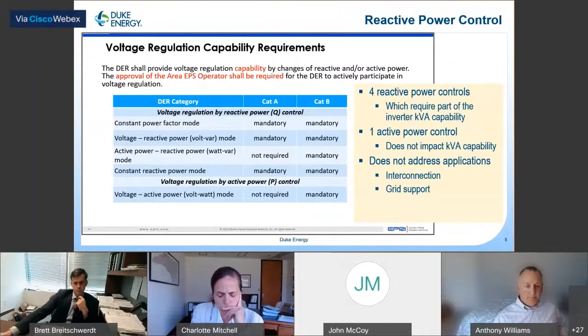A good bit of effort is put into clarifying tripping for events and capability to ride through in the standard. These are two of the main sections: 641 involves tripping, and the second requirement focuses on the capability of the DER to operate until it trips.